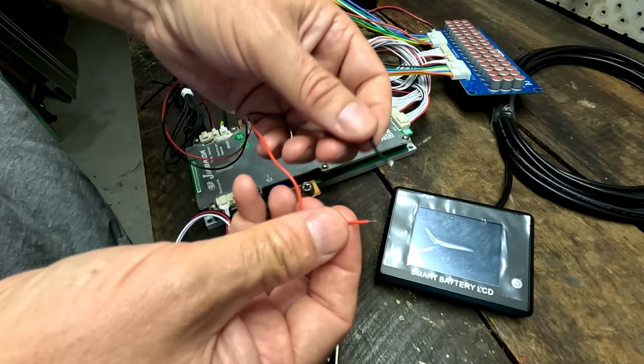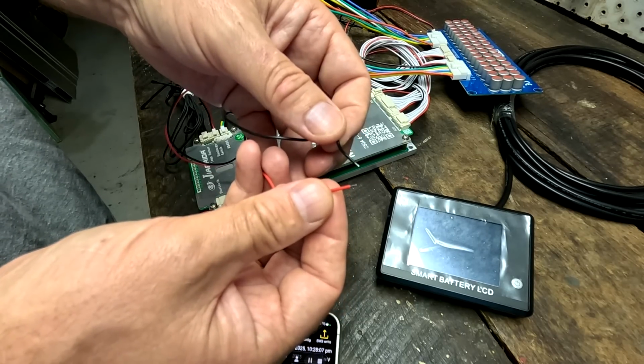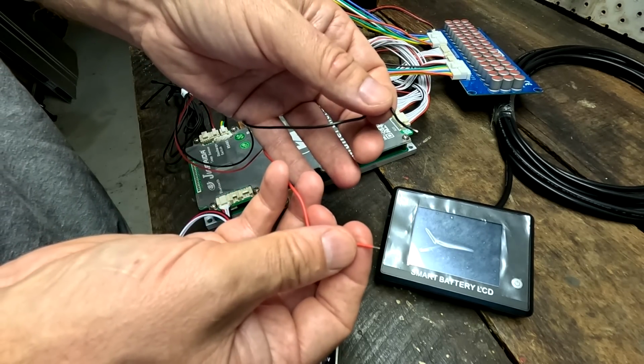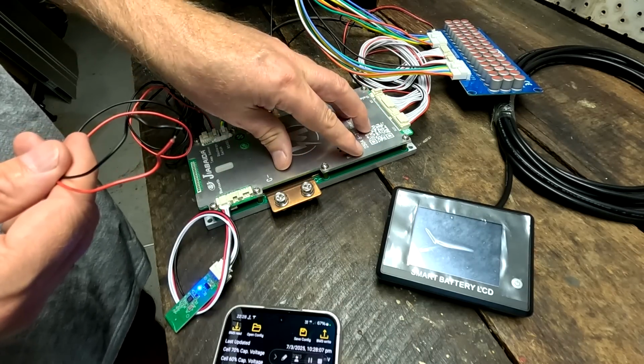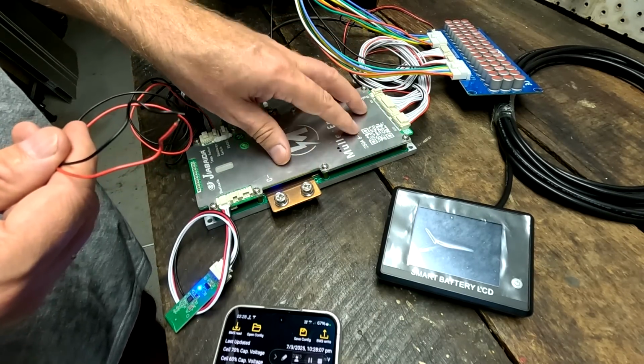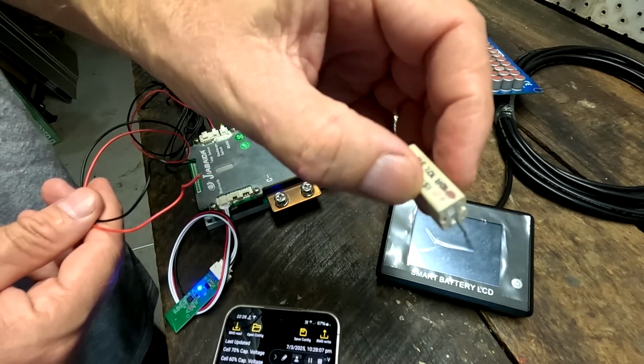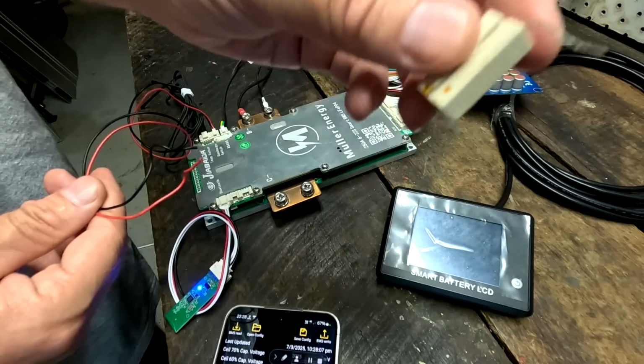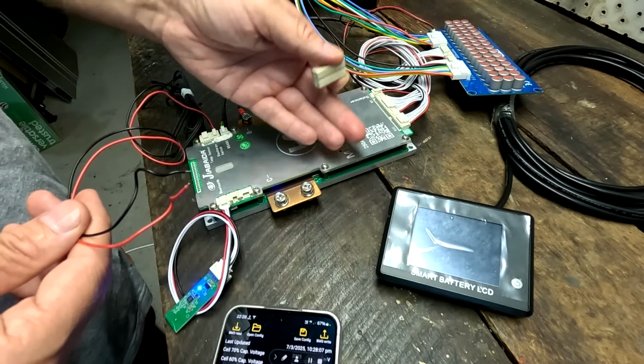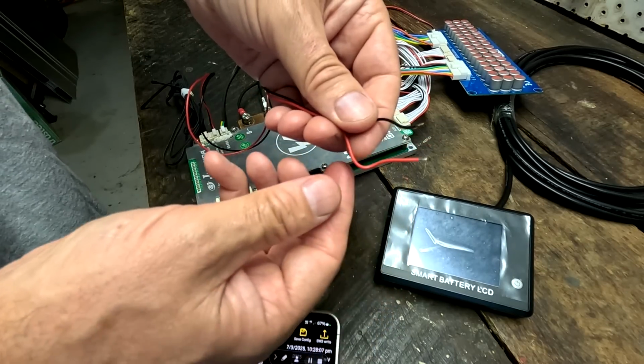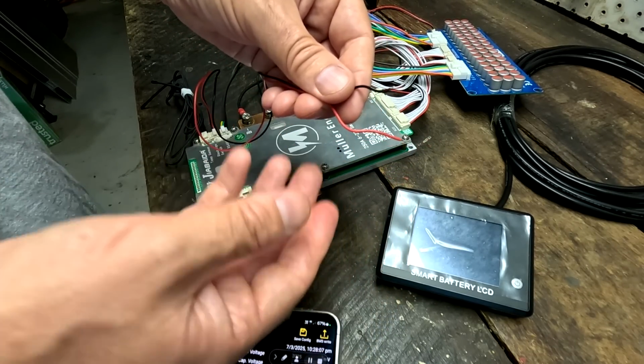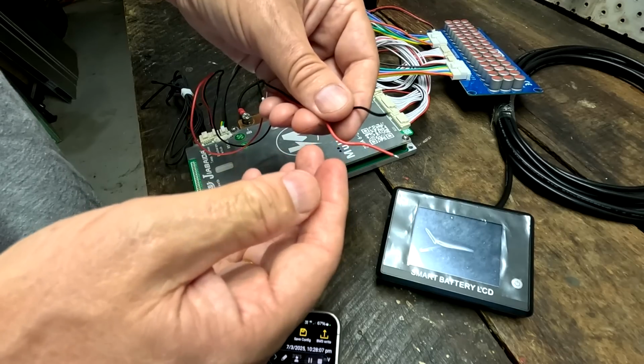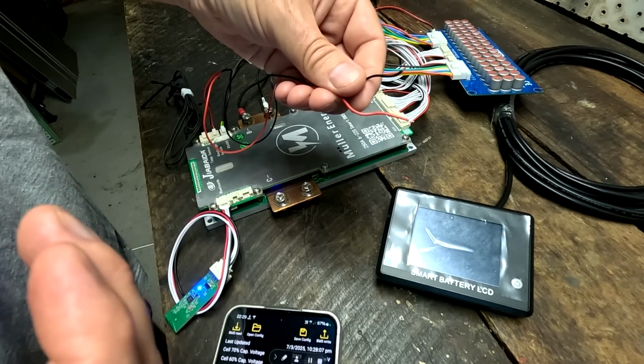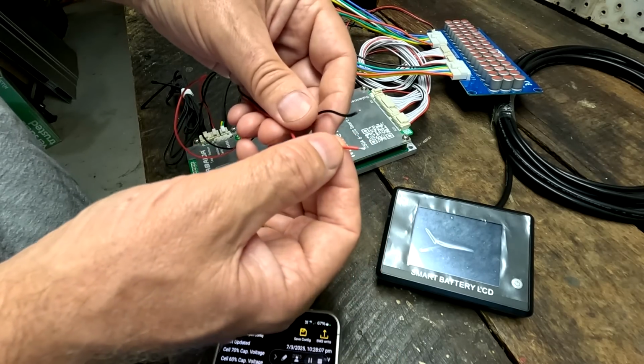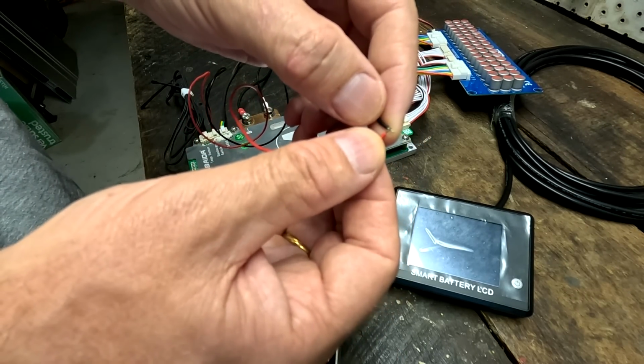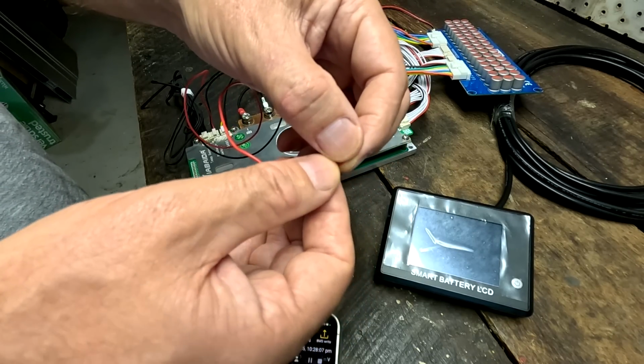What is the purpose of this? You can turn off the discharge MOSFETs and then safely connect your inverter, for example. If you go camping and have an inverter that frequently connects and disconnects to your battery, you'd need one of these pre-charge resistors to pre-charge the capacitors in your inverter, to avoid a big spark and inrush current through the BMS. But with this function, we can turn off the discharge MOSFETs of the BMS, so when you connect your inverter, there's no power going from the battery through the BMS into these capacitors. Once the inverter is connected, you just connect these 2 cables with your switch and it turns the discharge MOSFETs back on, charging the capacitors inside your inverter.